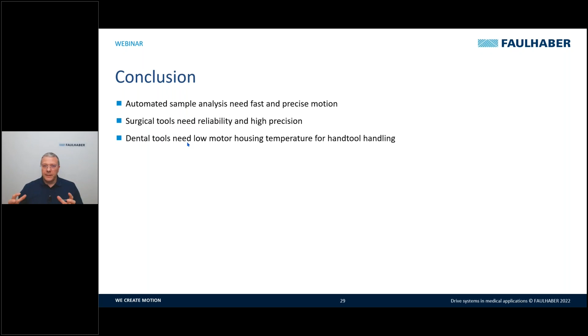So we have reached the end of this webinar for now. Just to summarize everything, we have seen that different types of application need a different type of drive system. For example, sample analysis, surgical tool or dental tool, they need different characteristics of the drive system. The coreless motor has a linear behavior between the applied voltage and the motor speed, and the current of the motor and the delivered torque. We have high dynamics, and this is ideal for high precision direct drive operation. We have high efficiency motors for battery operated medical devices.